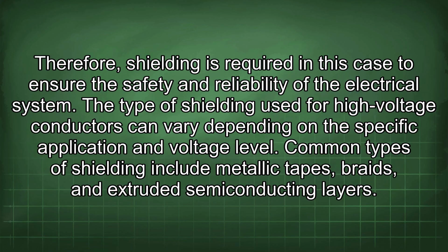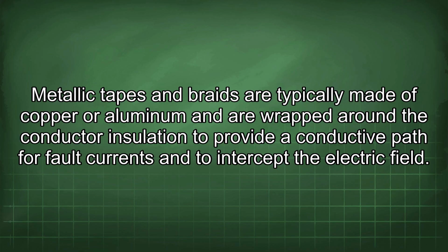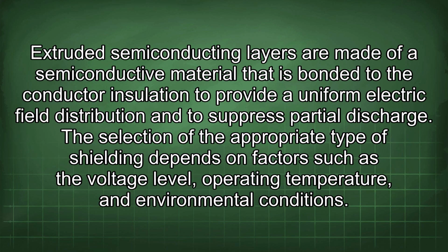The type of shielding used for high-voltage conductors can vary depending on the specific application and voltage level. Common types of shielding include metallic tapes, braids, and extruded semiconducting layers. Metallic tapes and braids are typically made of copper or aluminum and are wrapped around the conductor insulation to provide a conductive path for fault currents and to intercept the electric field. Extruded semiconducting layers are made of a semiconductive material that is bonded to the conductor insulation to provide a uniform electric field distribution and to suppress partial discharge.